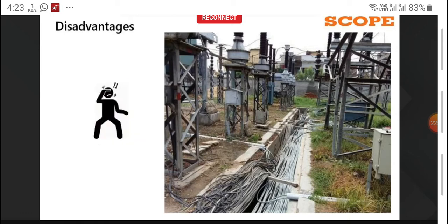And second, he cannot segregate the main cable from the problematic cable. So mostly you see unwanted tripping happens, and when you go to the protection relays everything seems normal, but unwanted trippings are happening on the line, or on the transformer, or in some other area. If you trace out what exactly the problem is, you will be surprised to know that many unwanted trippings are due to DC leakages through these damaged cables. The battery also normally gets drained quickly due to these leakages, cable breakages, cable rusting problems, all these things. So it is very difficult for a site engineer to understand and rectify it.